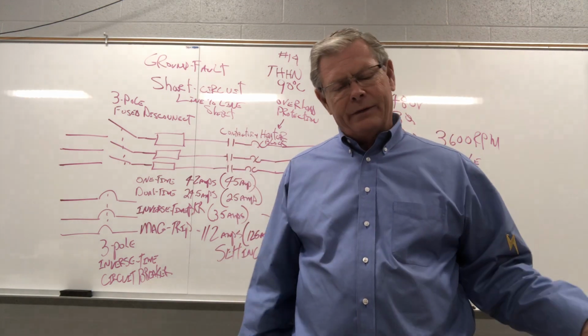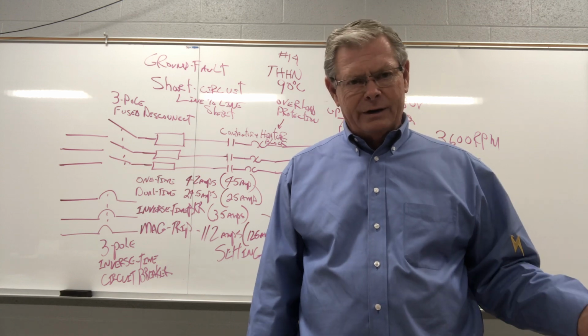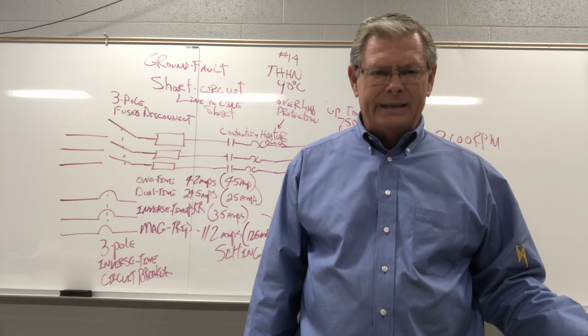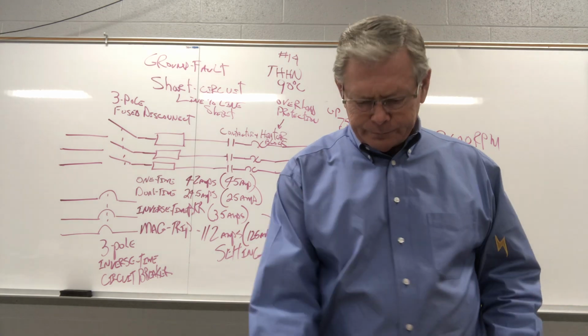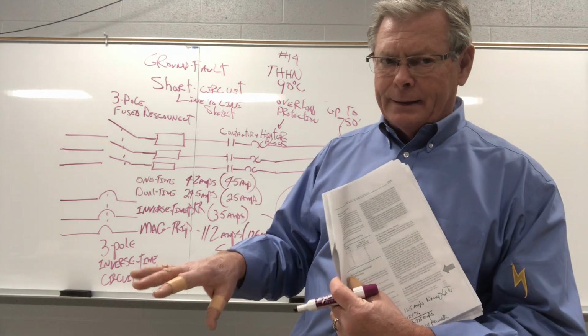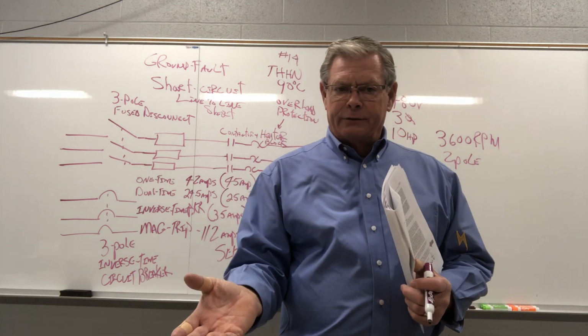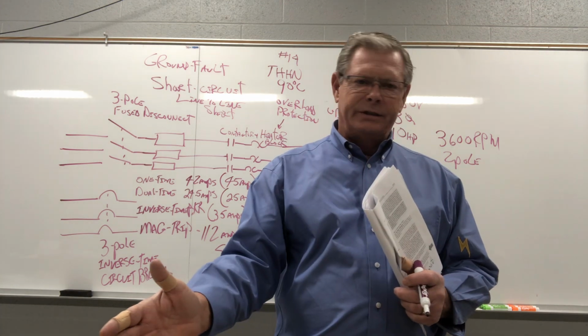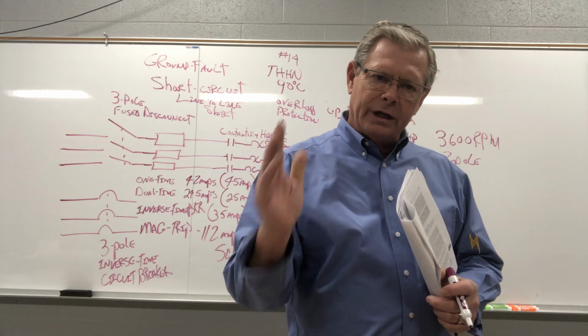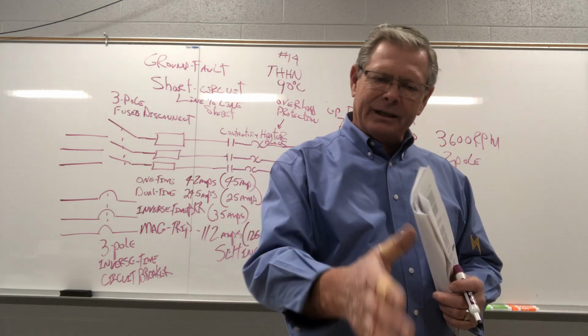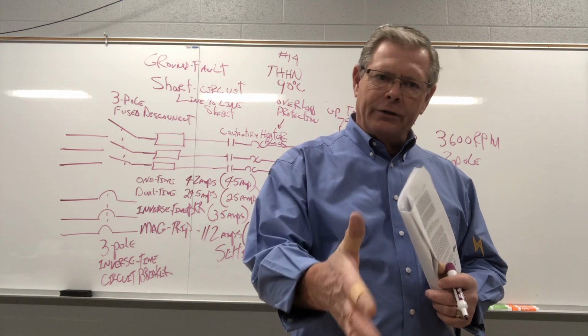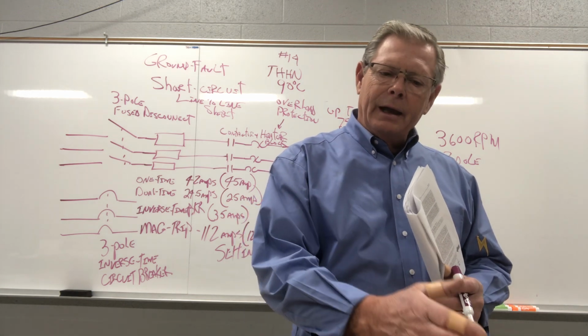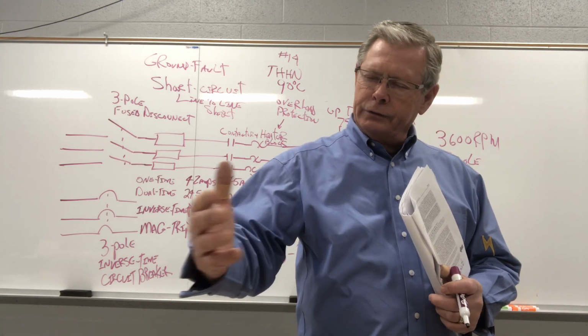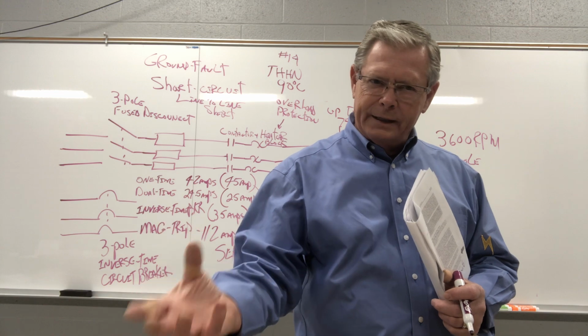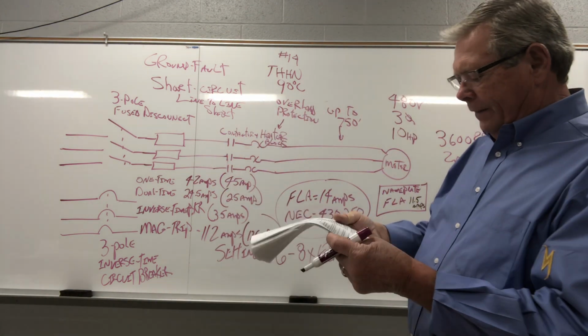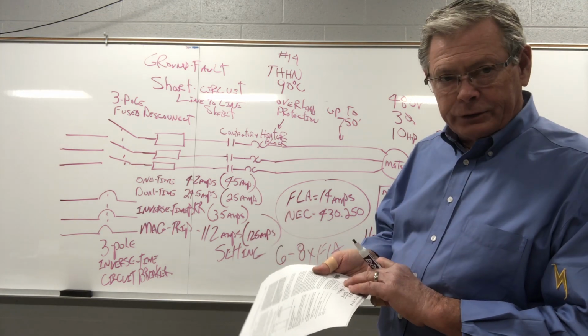That same motor, if you go out there whenever it's 0 outside, 40 degrees C over 0 is a pretty good place to sit on to warm up, you know? So just know that's 40 degrees C over ambient. A good way for me to look at a service factor of 1.0, if it's a 10 horse motor, is 10 horse motor. But a 1.15 is really 115% of a 10 horse motor. Or a 1.35 is 135% of a 10 horse motor. The higher the service factor, the stouter the motor's built, the more rugged it is. So, we're going to say that this motor has a 1.2 service factor.